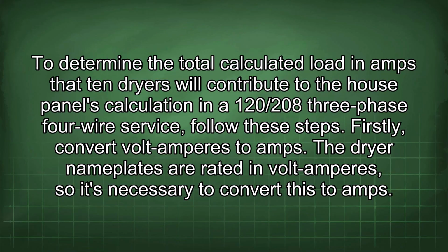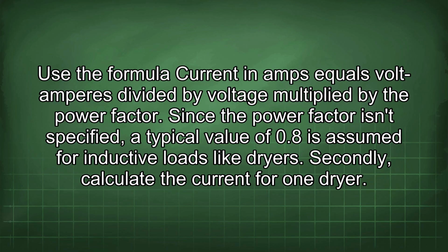To determine the total calculated load in amps that 10 dryers will contribute to the house panel's calculation in a 120/208 three-phase 4-wire service, follow these steps. Firstly, convert volt-amperes to amps. The dryer nameplates are rated in volt-amperes, so it's necessary to convert this to amps. Use the formula: current in amps equals volt-amperes divided by voltage multiplied by the power factor. Since the power factor isn't specified, a typical value of 0.8 is assumed for inductive loads like dryers.